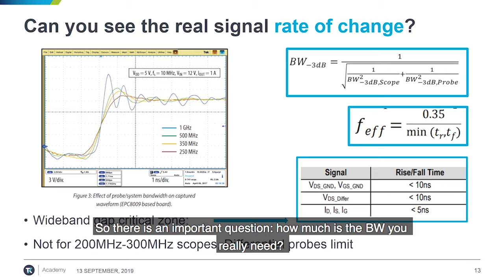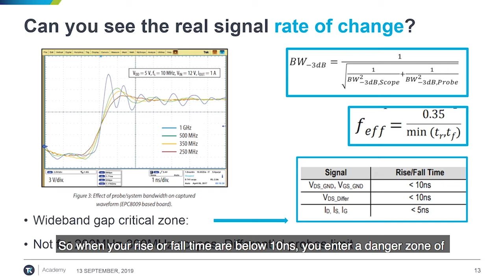Well, it's a simple calculation to do, coming from signal theory. There is a formula giving you the effective bandwidth of a signal with rise time TR and fall time TF. And once you get this number, the whole system bandwidth should be 3 or 5 times higher than the maximum equivalent frequency of the measured signal for the magnitude, and much more for the phase. So when your rise time or your fall time are generally below 10 nanoseconds, you enter a sort of danger zone of inaccuracy with your existing test system built around a 200 megahertz reference bandwidth.